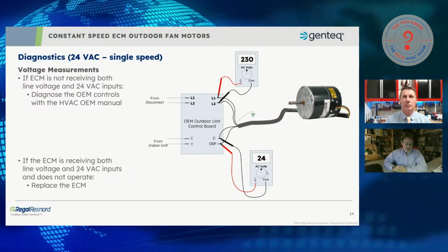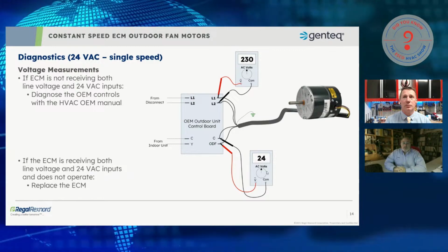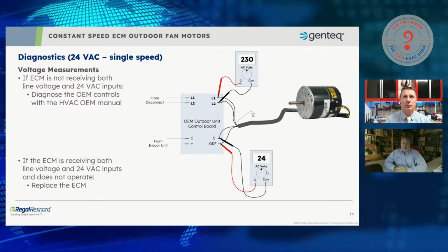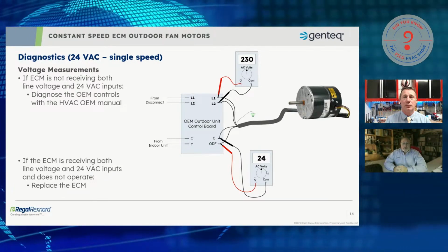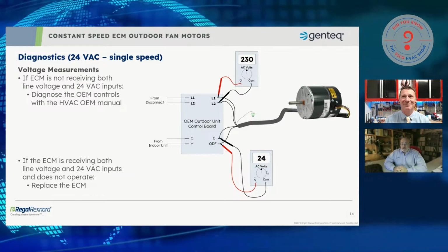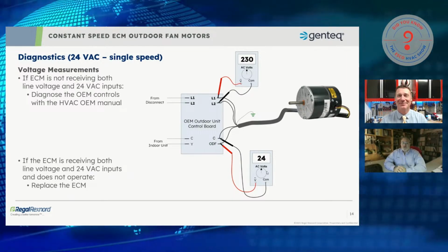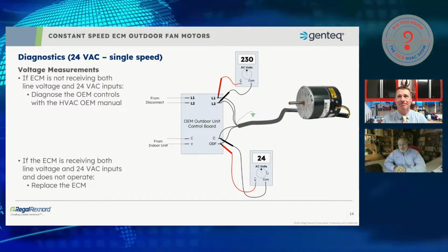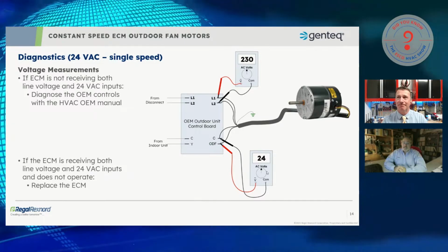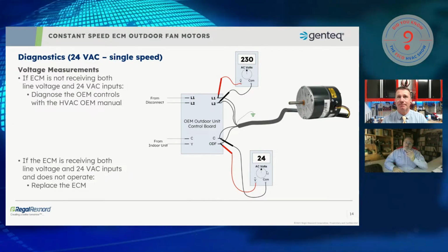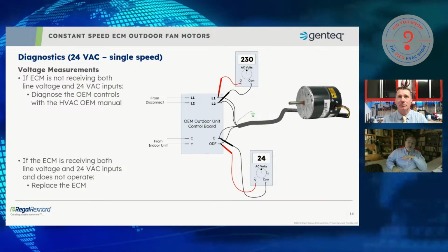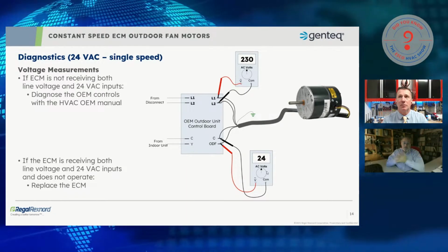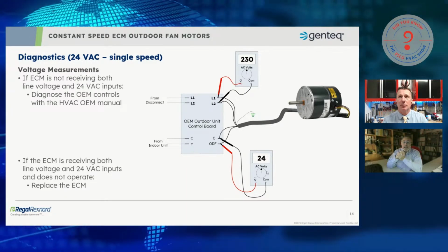I provide tech support for our motors, and with these motors, I spend the most time answering the same question over and over. Are you sure the motor's failed? You have both voltages going to the motor, it's not running. Yeah, but shouldn't it? It's just that simple. It's just those two voltages. I also get asked, well, should I separate the motor and ohm out the motor to see if the motor is good or bad?